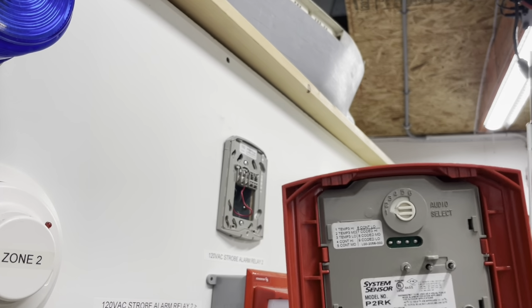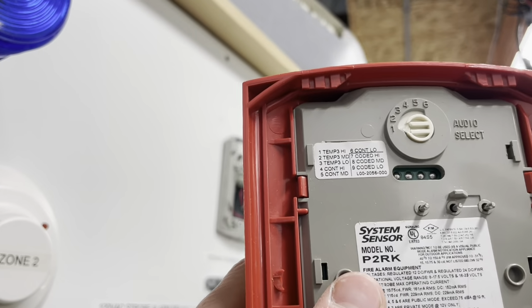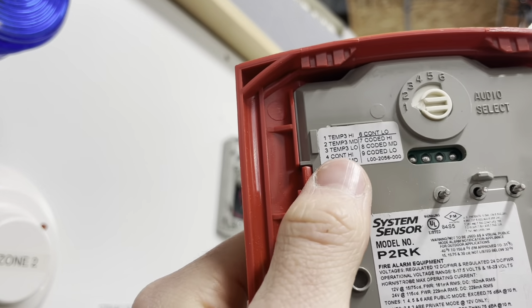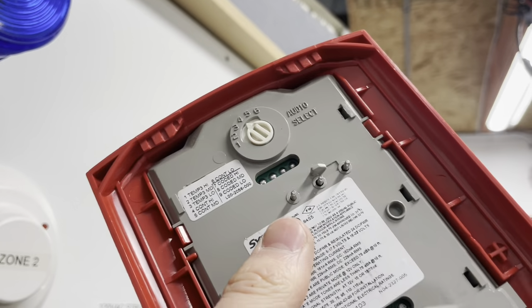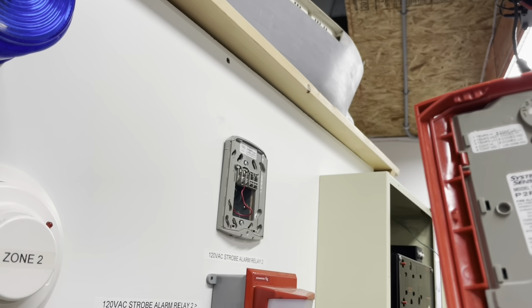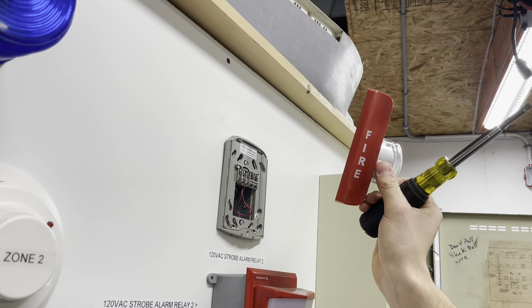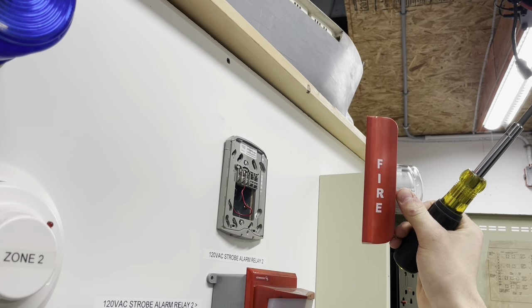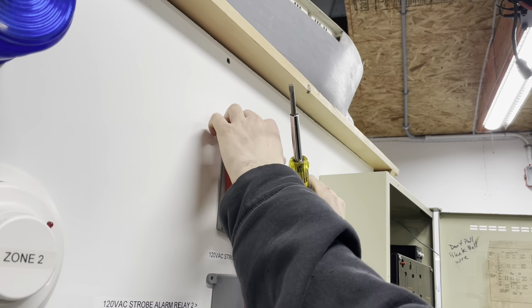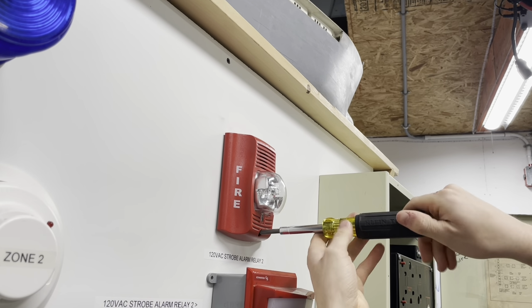This device comes from the factory set to temp 3 high volume. Number one, we want it on 4, continuous high, just to be fair to the bell, because the decibel meter will sometimes slightly get a louder reading after it's been ringing for a while, and temporal 3 wouldn't do that, so it's only fair that we leave it on continuous.